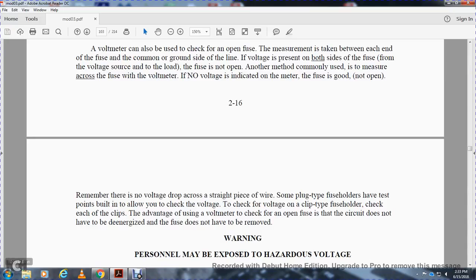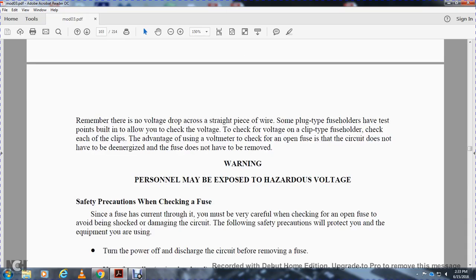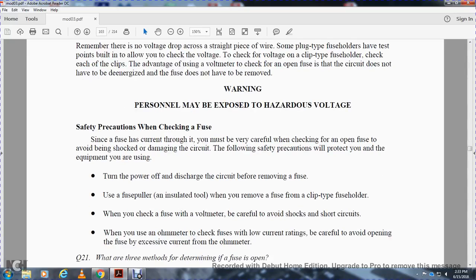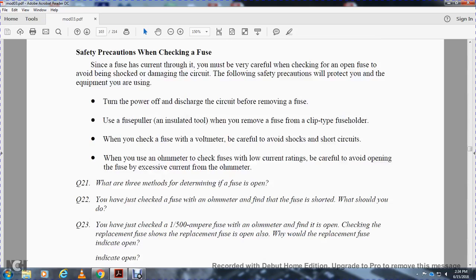Warning: personnel may be exposed to high voltage. Safety precautions when checking a fuse: if the fuse is currently in a live circuit, you must be very careful when checking and opening the fuse to avoid shock. The following safety precautions will protect you and the equipment: turn the power off and discharge the circuit before removing the fuse. Use a fuse puller or insulated tool to remove clip-type fuse holders. When checking the fuse with a voltmeter, be careful to avoid shocks and short circuits. When checking fuses with low current ratings, be careful to avoid opening the fuse with excessive current from the ohmmeter.